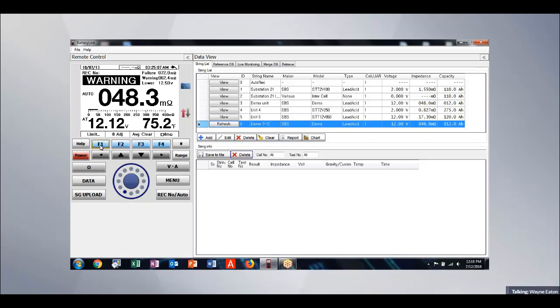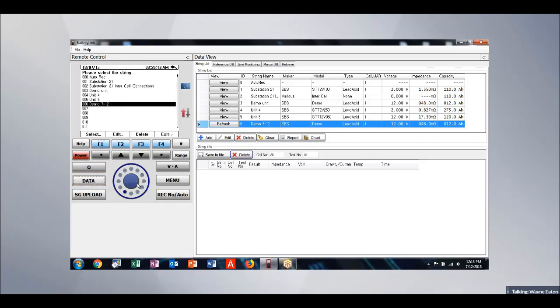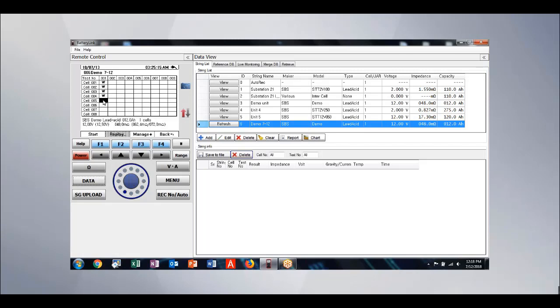So now I get a good recorded reading in its place. If I go back in and look at that data now, you'll see that I got rid of that negative, and now it's got the positive value for that voltage in it. So one of the things I recommend with the 6500 is, anytime I get a warning or a failure and I'm not expecting it, I can always go back and take another reading to verify that it is actually a bad reading or a warning reading, rather than just misplacement of the probes or having the wrong polarity or something.